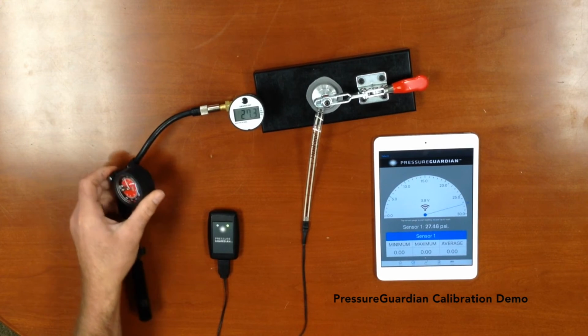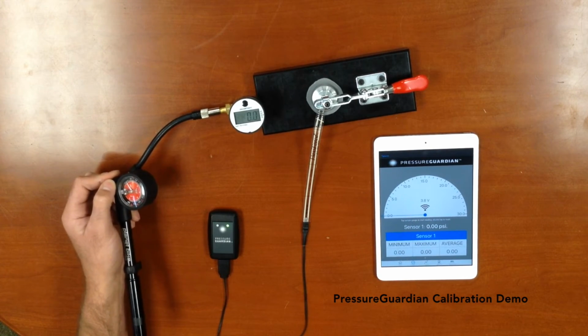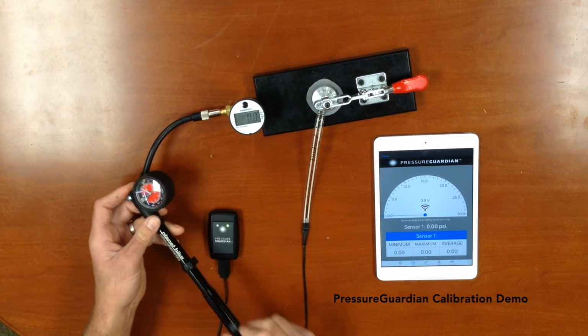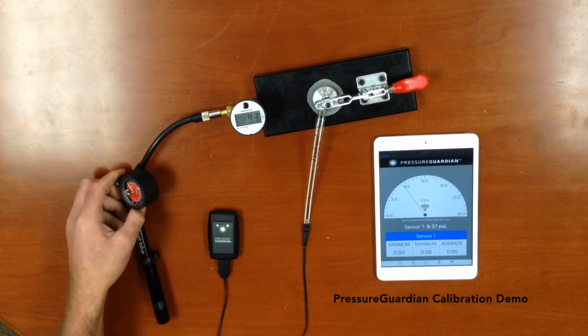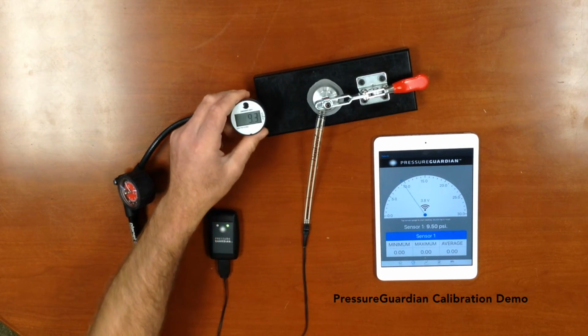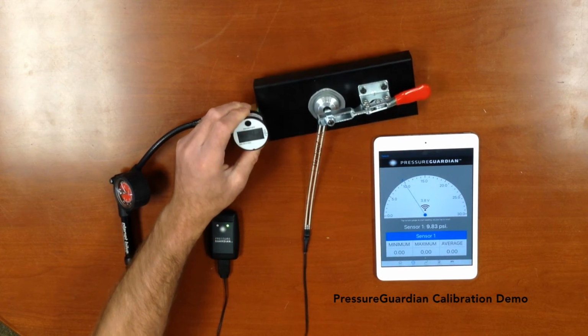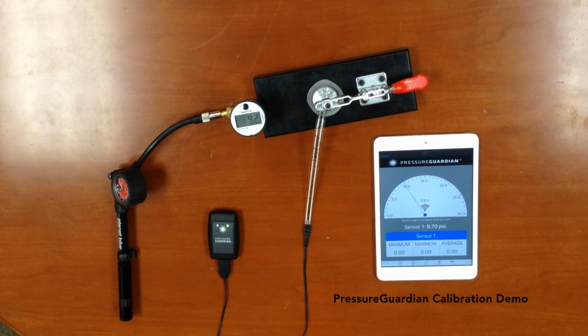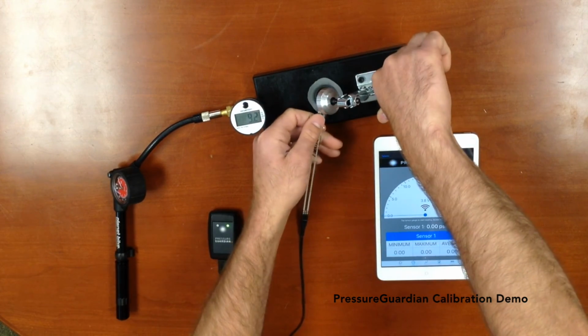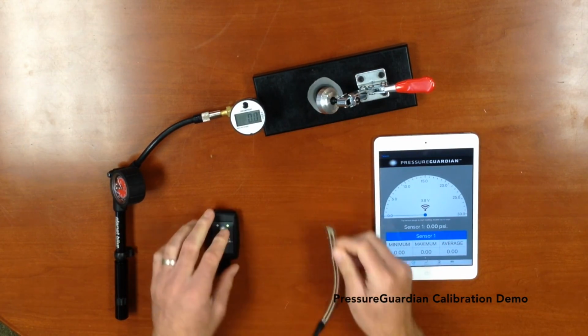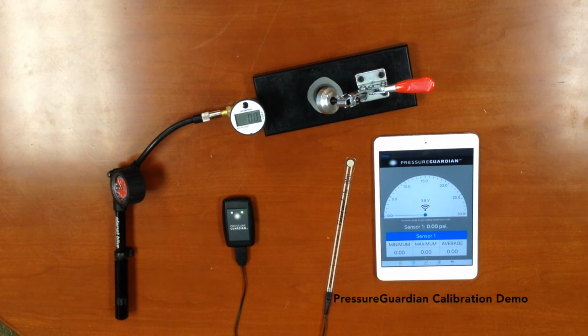So now we can drop and bleed all the air out of the system, and then I'm going to give 1 full pump again. We're going to read our gauge at around 9.5 psi, and our PSI is holding around 9 to 9.5. This system is completely calibrated and ready for use. We can take it out of our jig and place it in the device and pressure measure the areas where we want to measure.